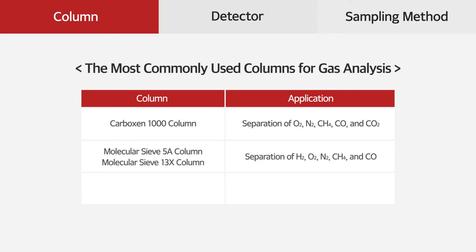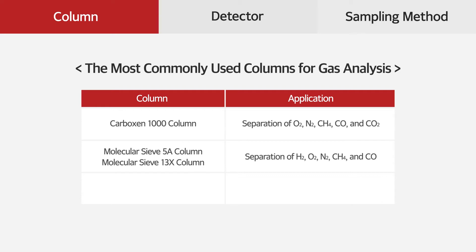Molecular Sieve 5A and 13X columns improve the separation of permanent gases and have good resolution for carbon monoxide. But they are not suitable to separate carbon dioxide and hydrocarbons over C2, because these compounds easily get stuck into the column. So it is important to condition the column to get rid of moisture and carbon dioxide that might be absorbed in the column when you get a new one.